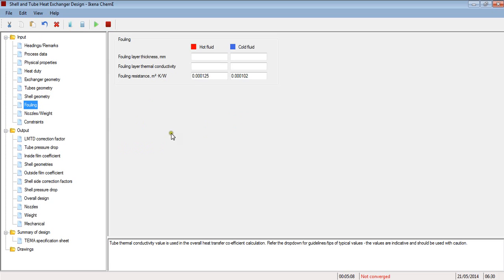Here you can enter the fouling information. As you know, fouling is a complex phenomenon, and it cannot be defined properly by just specifying fouling resistance, but much work is to be done to come up with models that can predict fouling accurately or the life of a heat exchanger. So we will just use the simplest method and specify the fouling resistance. You can also specify a thickness for your scale and its thermal conductivity, and the program will calculate the fouling resistance for you. But since we have already specified fouling resistance, we will leave these two values blank.